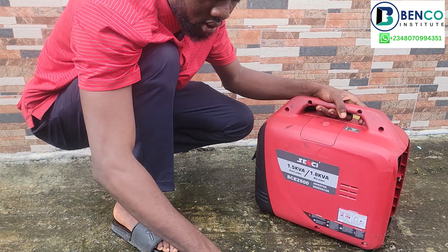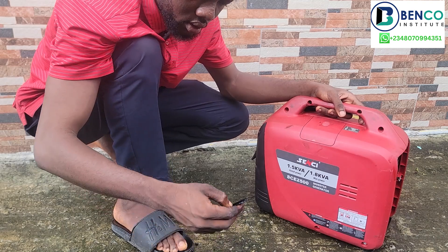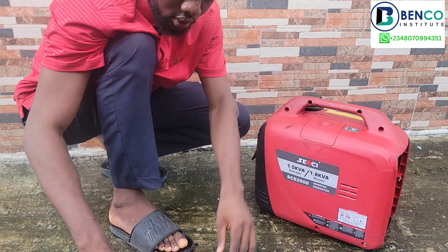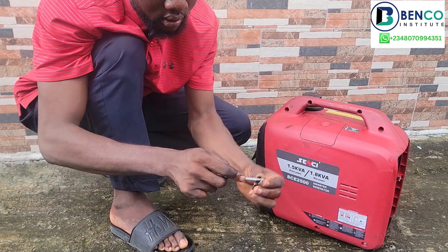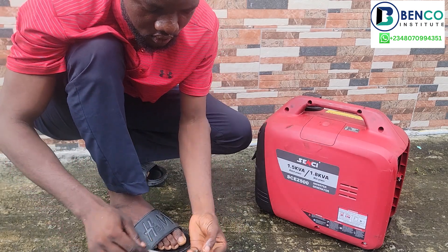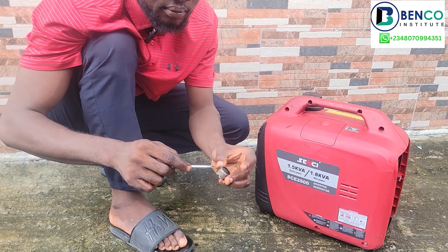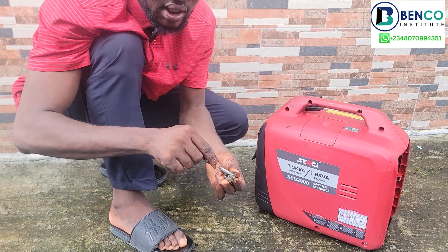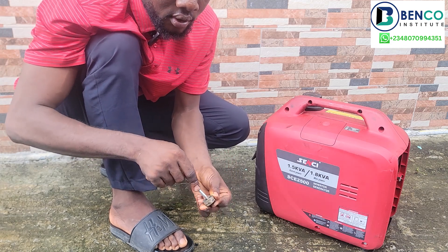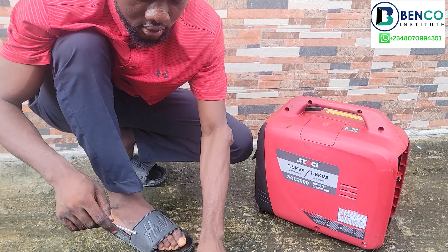We'll just put this in and leave it for about five minutes so that all the carbon will come out. The aim is to free the filter — take off the carbon from the filter — so the generator can breathe properly. This is clean enough now, a stark difference from what it was before.